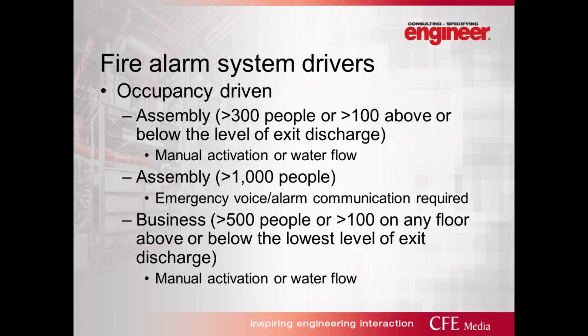Now, the activation of the fire alarm system may be by manual activation or maybe by automatic activation, such as an alarm initiating device like water flow or smoke detection or heat detection or some other mechanism, right? Now, in assembly occupancies where we are over 300 people at grade level or more than 100 people above or below the level of exit discharge, we do have a requirement for fire alarm. So we might have a sprinkler requirement, and you could actually have a sprinkler requirement in the building without a fire alarm requirement. So that does occur.